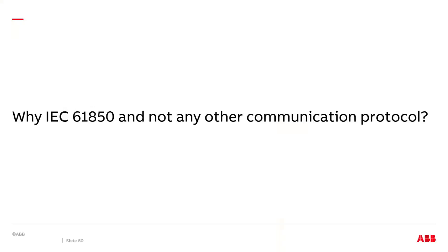So why are we using IEC 61850 and not any other communication protocol like Modbus, TCP/IP or DNP3? Because IEC 61850 is an open and global standard for power system applications. It actually defines all the objects that are there in your single line diagram. It also enables interoperability between multiple different vendors, because they all work on the same substation configuration language, and it's all based on the data modeling that is done similarly with every vendor program. And it has three different things that you can achieve with it: GOOSE communication, MMS, and sampled measured values.